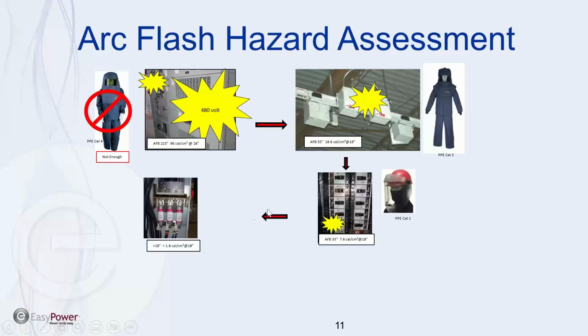And then downstream from there, we've got fuses. And downstream from the fuses, it's going to be extremely low because fuses are fast. And the good thing about fuses as well is they don't require maintenance. They're going to be operating at a very low level or opening up. So downstream, we're still in this panel, we're still in a shield.